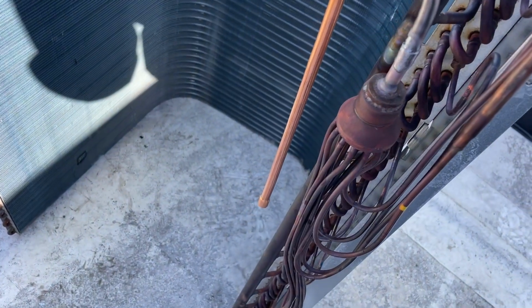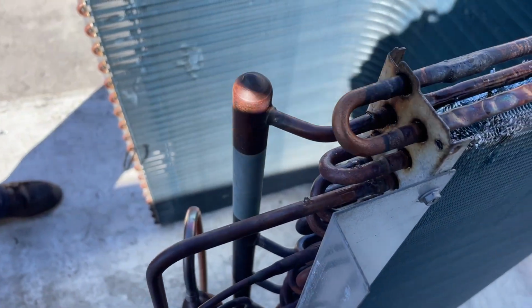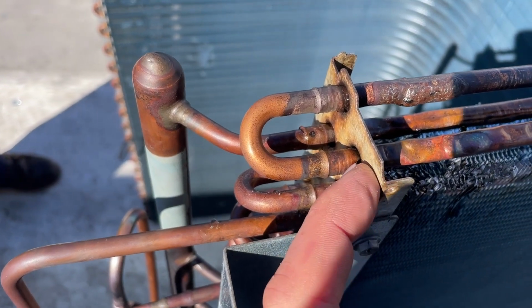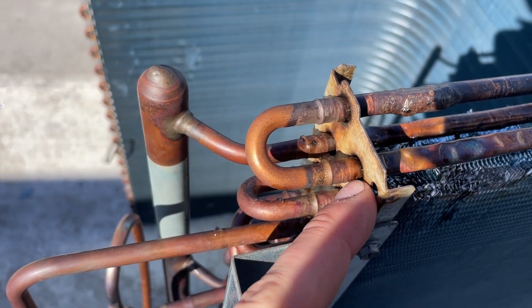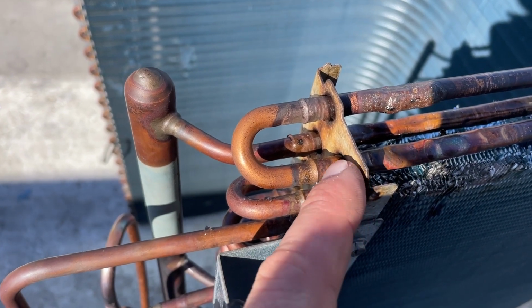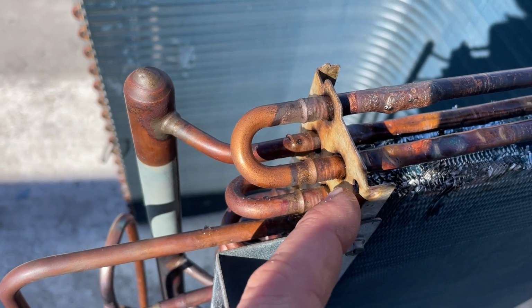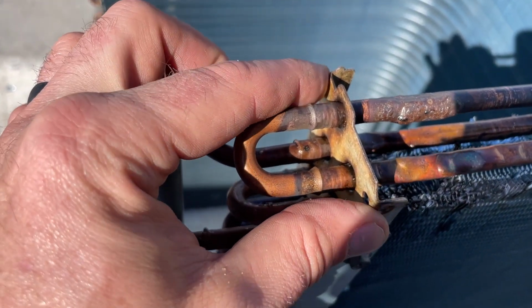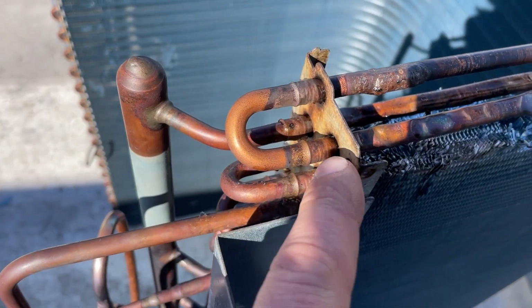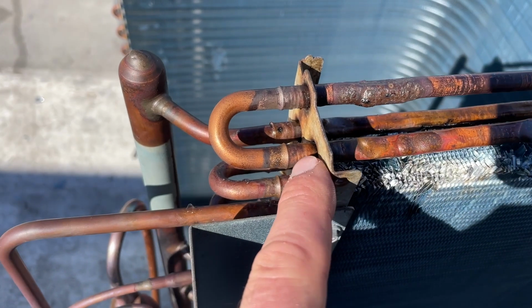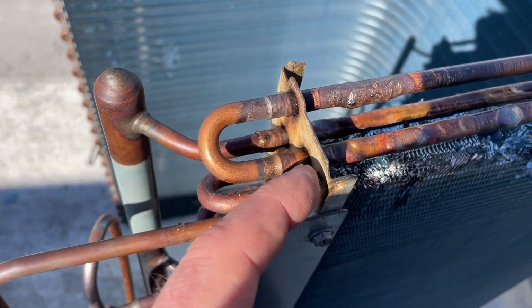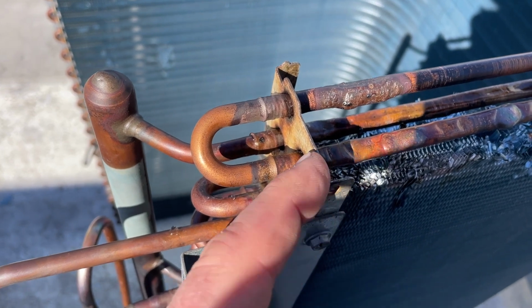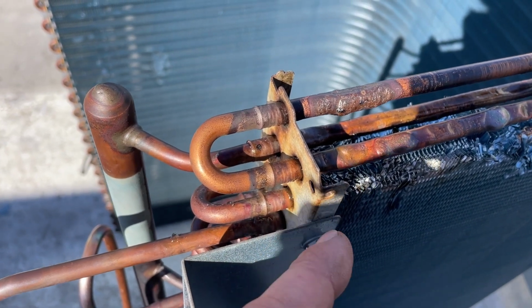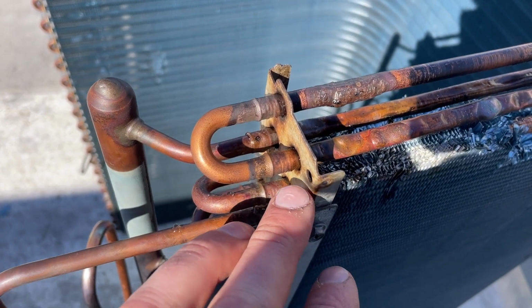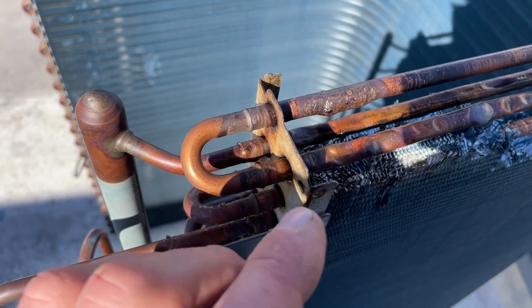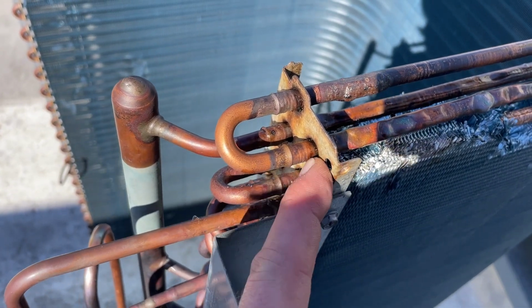Got a new tube on the little squiddy there, let me talk about something real quick. If you happen to have a leak up in here, it's very common to get leaks right at that plate. The best way to handle that is to sand this area down really well, push the plate back and forward, try to get as good as you can in there. Coat this entire area with flux, and then take safety silver and actually braze this ferrous metal, this steel, right to the copper. You want safety silver for that for sure. You don't want to use a braze with phosphorus in it, and you want to use flux, but that is an extremely effective way to fix leaks on coils right here at this spot.